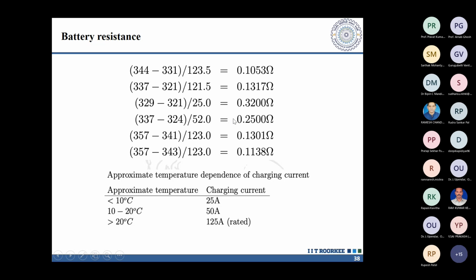So then you have to change the mode of operation from constant current to constant voltage mode. And also we require to maintain the temperature, so charging current at different temperatures will be different. For less than 10 degrees, charging current required is less; at 10 to 20 degrees you can maintain it to 50 ampere, and above 20 degrees centigrade you can maintain it to 125 ampere.